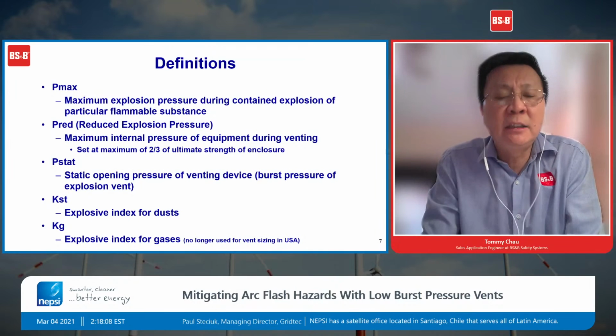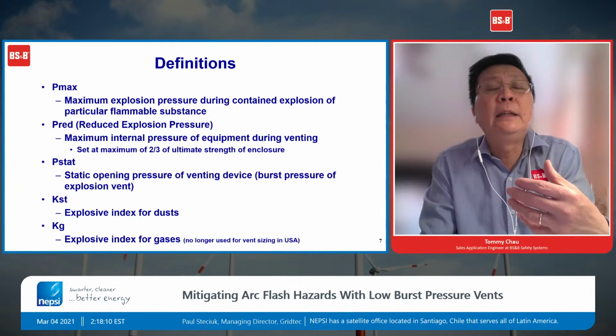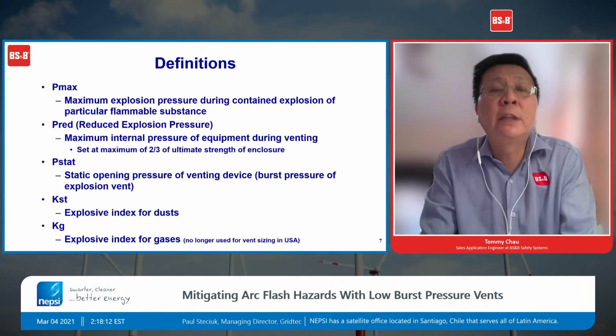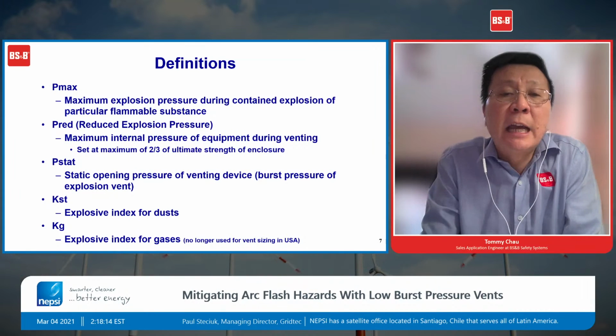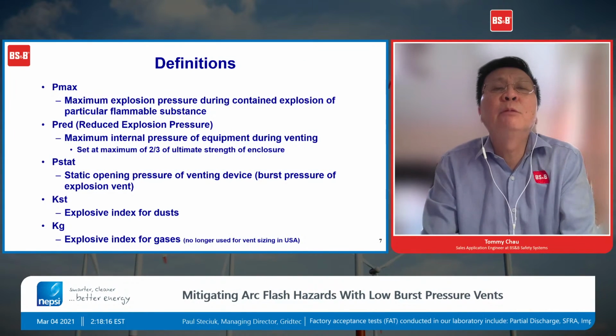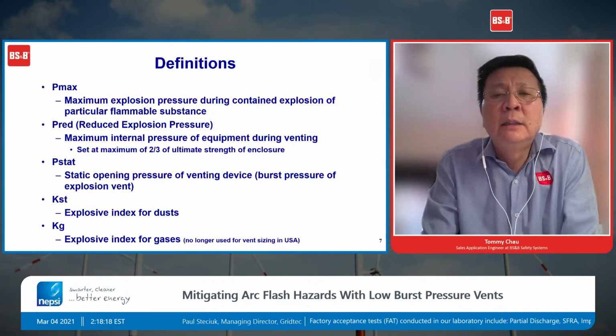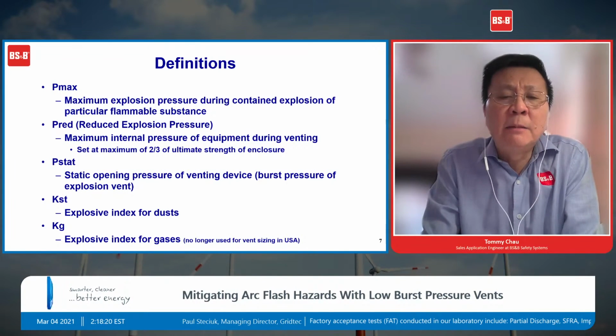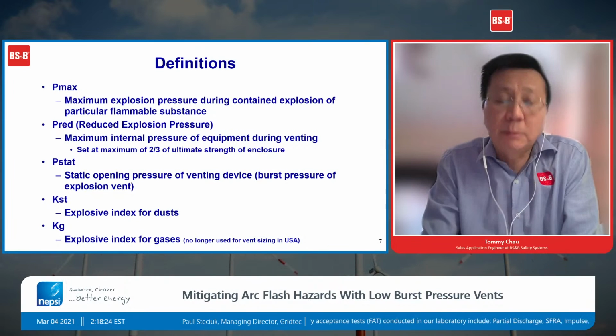So you have a KST value, which is an index for that particular dust, of how explosive it is. The maximum pressure, the Pmax, is what that product can see if you do not protect it with an explosion vent.